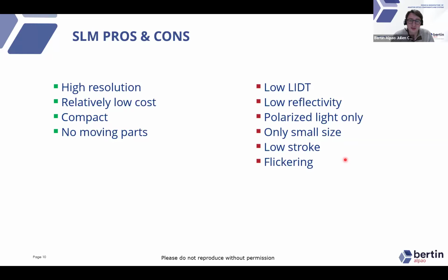And due to the drive electronics, there is some refresh rate on the full array of pixels, so you may have some kind of flickering, a small amplitude but global vibration on the wavefront. And again, depending on the application, this can be critical. For example, if you are looking at very high contrast or high resolution instrumentation, then this flickering effect, even if small, may be a complete showstopper. So the part that we want to address is mainly these parts. Just to mention that the laser power won't be much larger compared to a standard LCOS SLM, but we think we can really improve all the other drawbacks of the standard SLM.